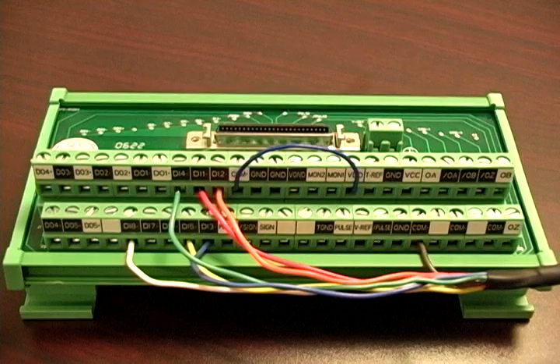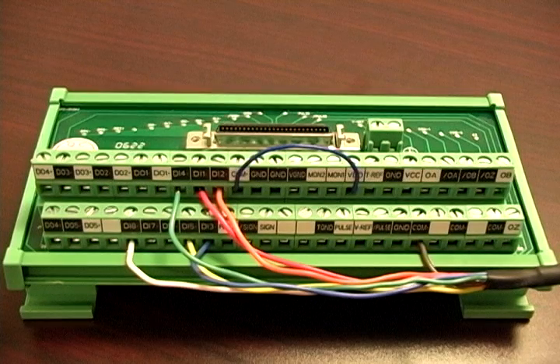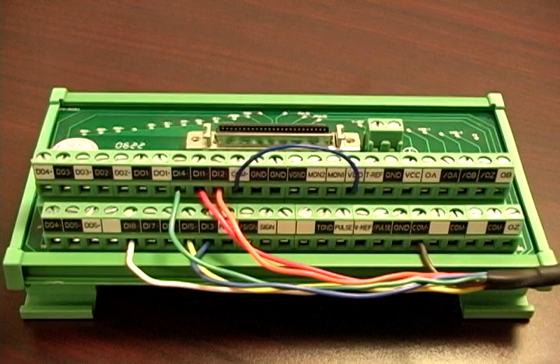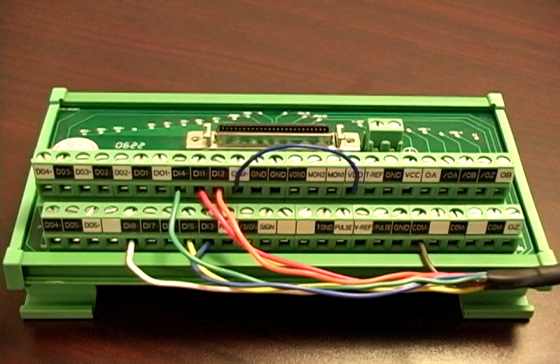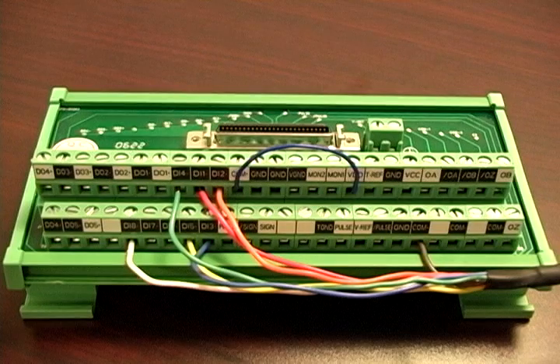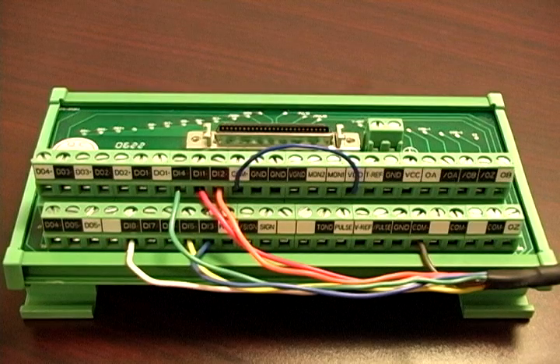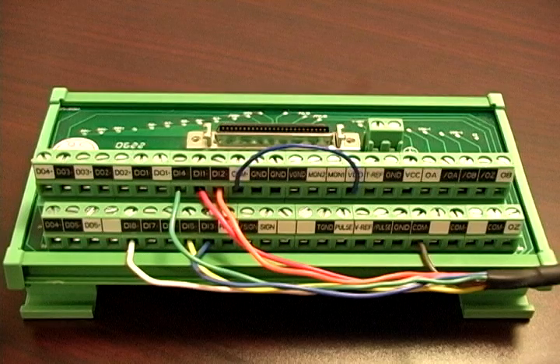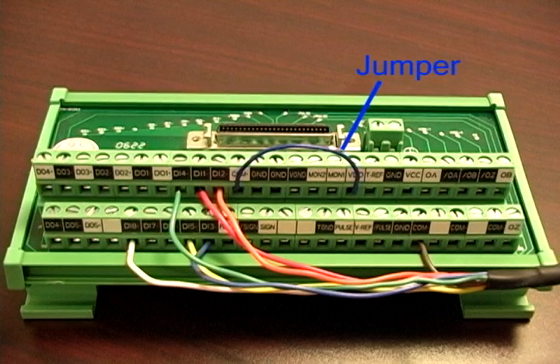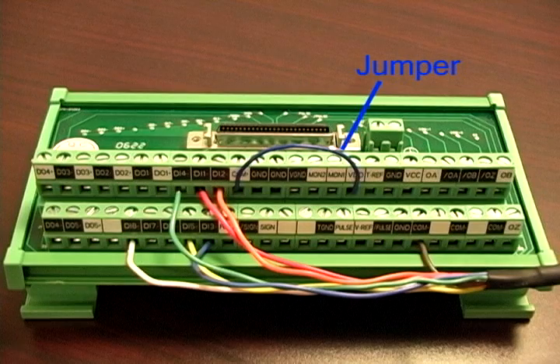The I.O. can be powered by external 24 volts, or you can use the limited 24 volts available on the drive. For this example, we'll use the drive's 24 volt supply. If your application is more complex, you should consider an external 24 volt DC power supply. To use the drive's internal 24 volts, you need to add a jumper wire from VDD to COM+.